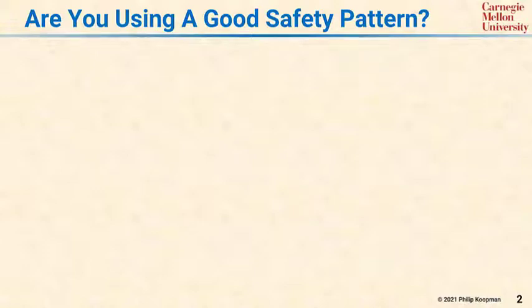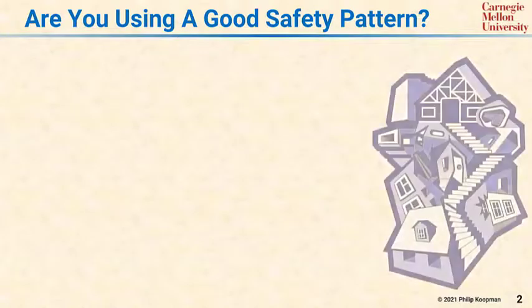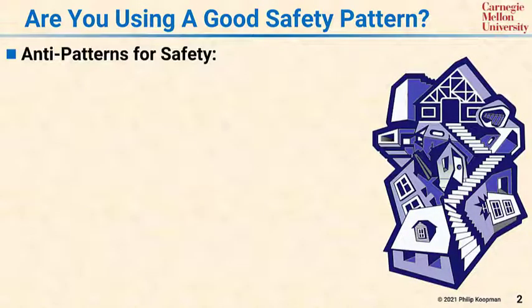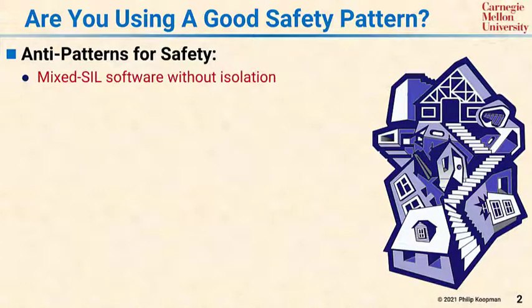Are you using a good safety pattern, or does your safety pattern for your system look like this crazy house? Here are some signs that you have a problem with the safety architecture of your system. First, if your system has multiple safety integrity levels — so it's a mixed-SIL system — but it does not have hardware isolation between the SILs, that's a problem.